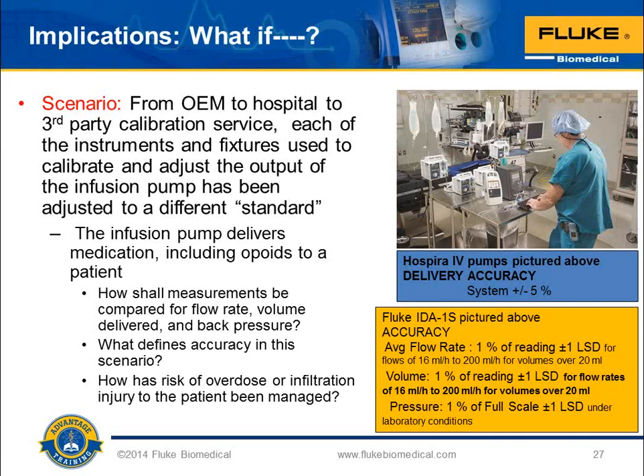How shall the measurements be compared for flow rate, volume delivered, and back pressure if we're unsure of what is the standard unit of measure? How would we do that otherwise if we didn't have a traceability chain that we could rely upon? What defines the accuracy in this scenario? If we can't be sure of the unit of measure, how do we know whether the device is accurate or our test instrument is accurate? And how has risk of overdose or infiltration injury to the patient therefore been managed?